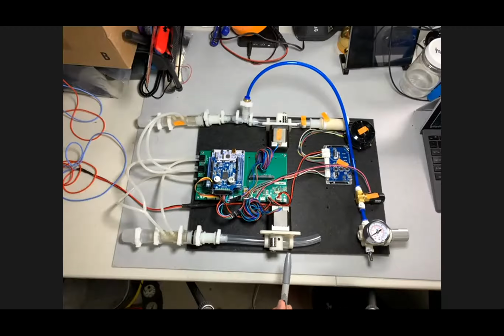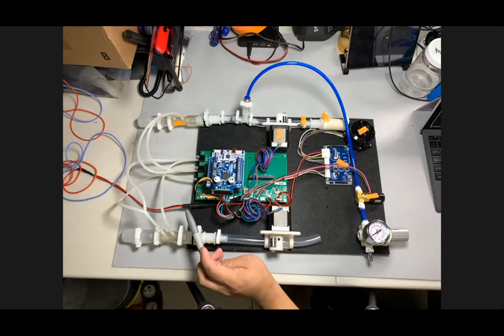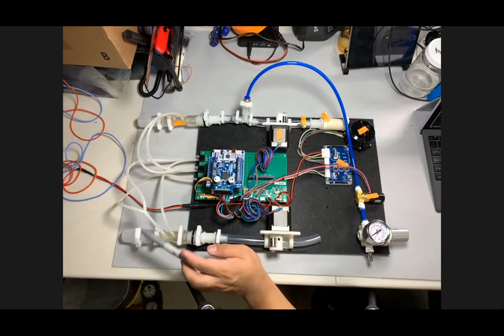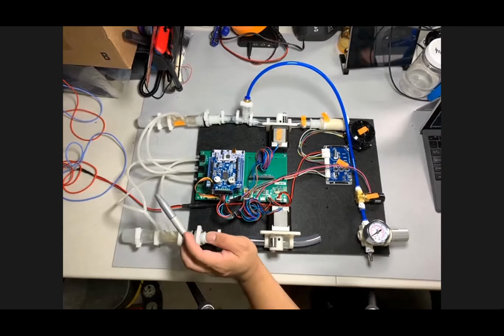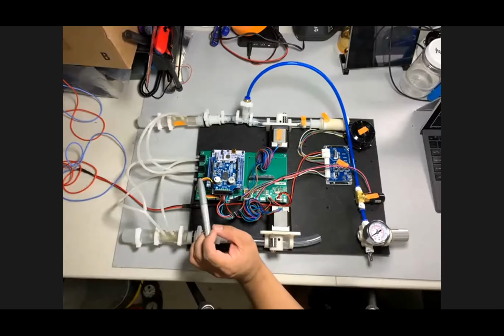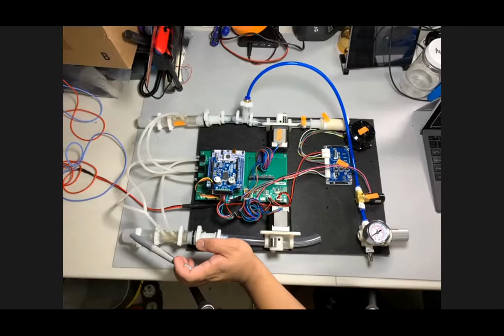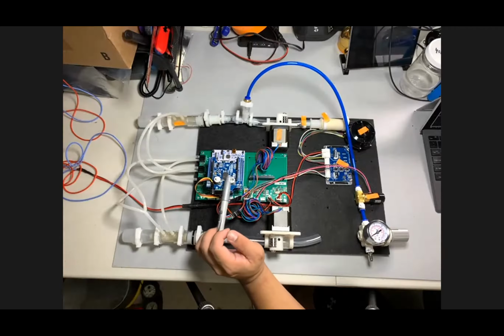Elizabeth asks, is there a reason why we are measuring patient pressure on the exhale rather than the inhale side? And the answer is there's no specific reason for doing that. It's a place to tap off the pressure. It could just as well be on either of these, and there will be a bias between them based on the resistance of the loop. So this is something that we will have to measure and compensate for in the final design. But for the purposes of the demo, as long as we have something that the controller is able to maintain control of the patient's pressure, it will work.